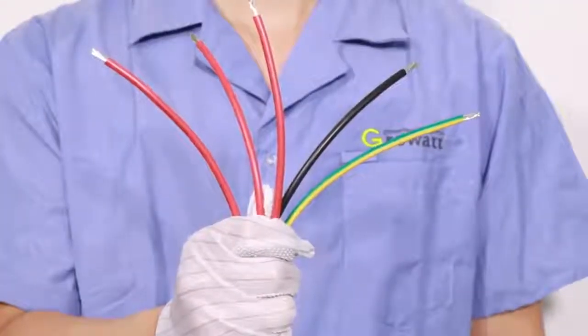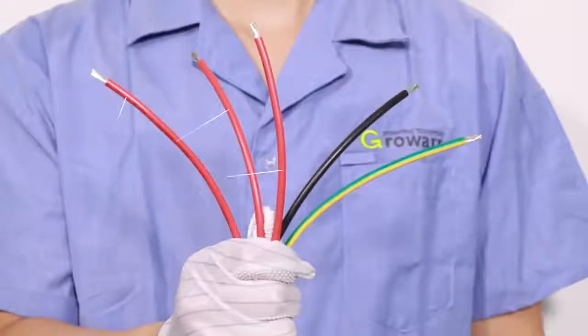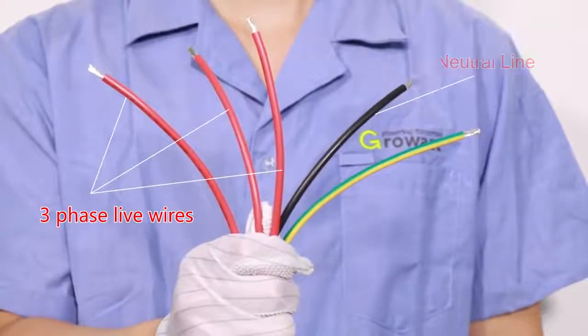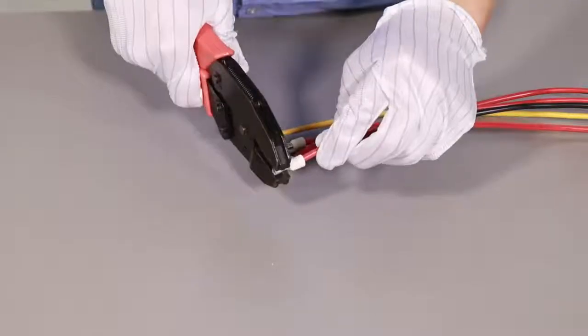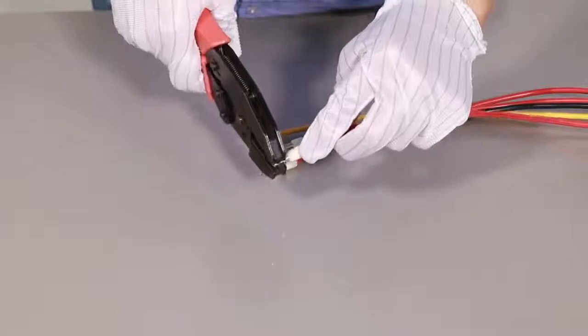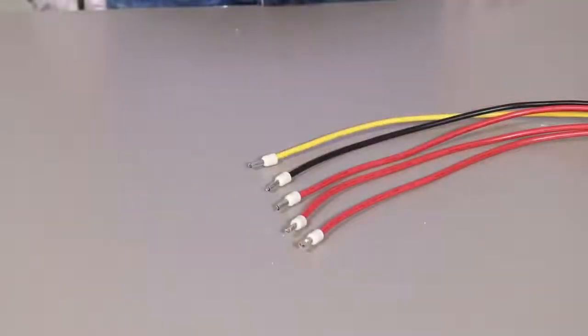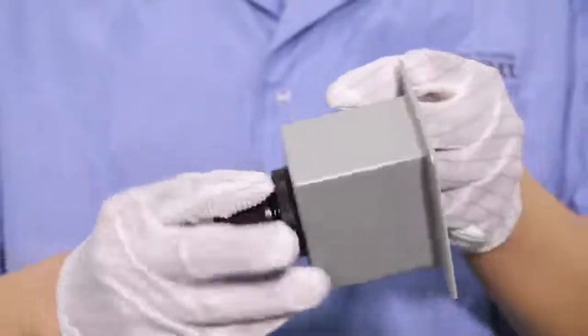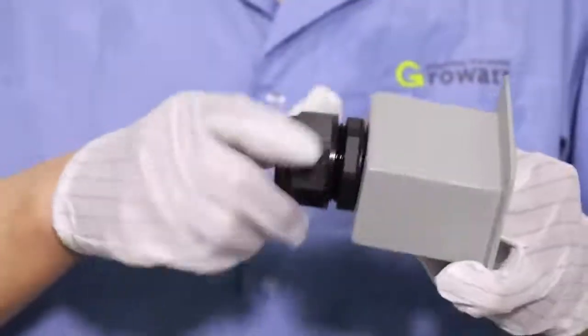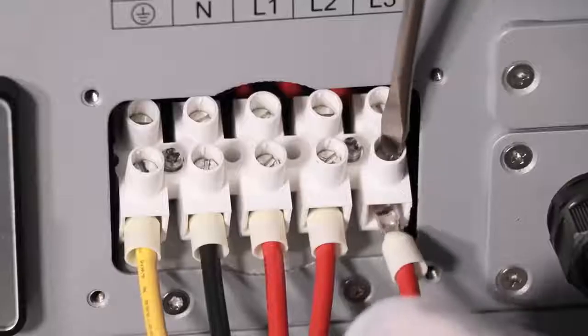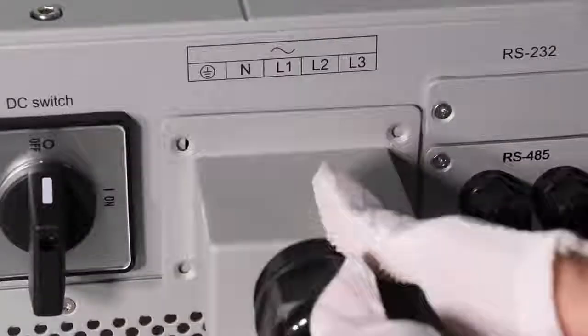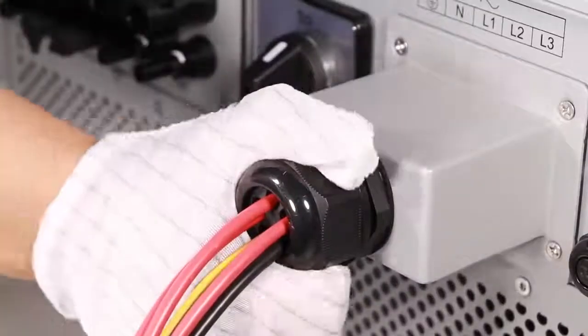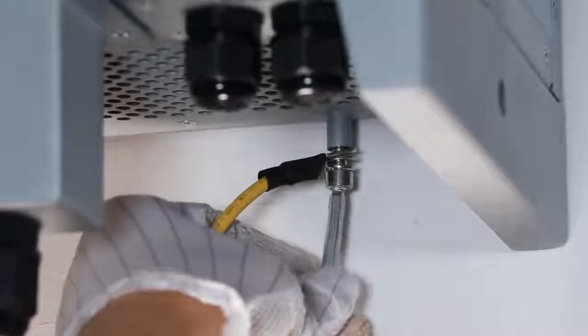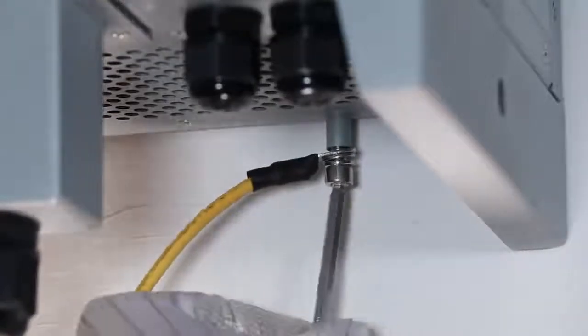The AC connection is a screw connector with 5 pins: line 1, line 2, line 3, neutral, and protection earth. Put the wire terminal to the lid. Use gripping pliers to tighten it. Put the cable to the AC protection cover, and then screw the 5 standard wires into the relevant terminals. It is suggested to earth an inverter frame via the earthing pole located in bottom of inverter.